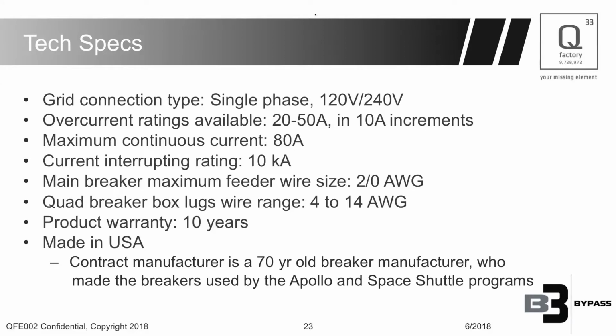There's a very small number of 3 aught 200 amp service panels that we would not fit on, but anything 2 aught or smaller will fit on. On the quad breaker, you can land generation or loads 4 to 14 AWG. The warranty is 10 years.